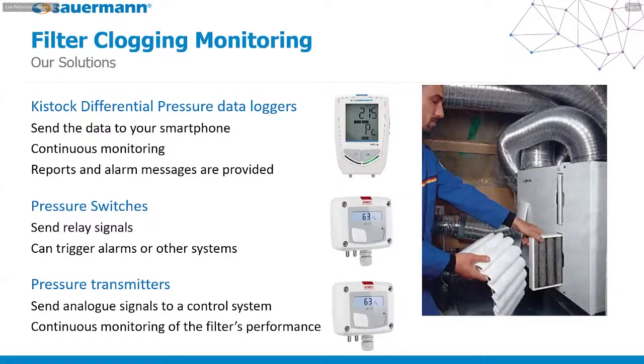Here's a very good example of how they can be used, especially, once again, for differential pressure. This can be either through a data logger or a transmitter. The reason you want to measure differential pressure in this case is that you have a lot of filters within your air handling unit and air handling system, because you want to minimize the dust in the rooms, because that can also be a health hazard. You don't want to get dust into the human lungs. So once again, that's why we have filters.